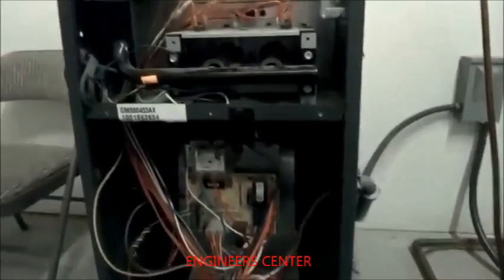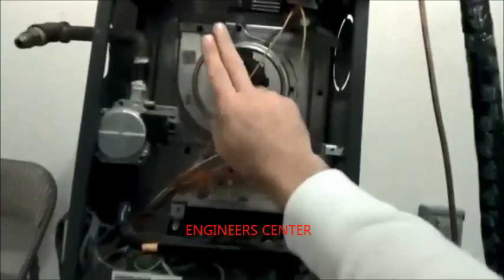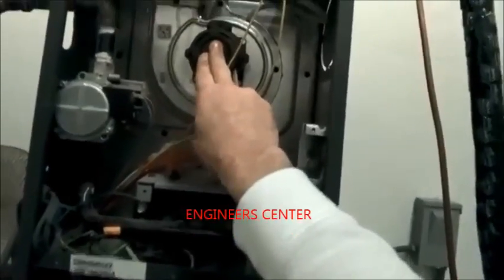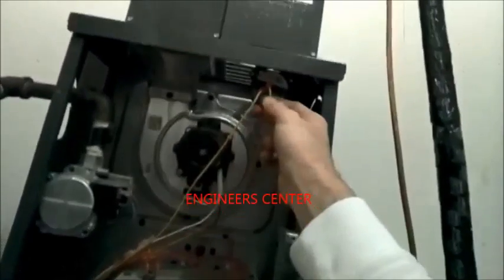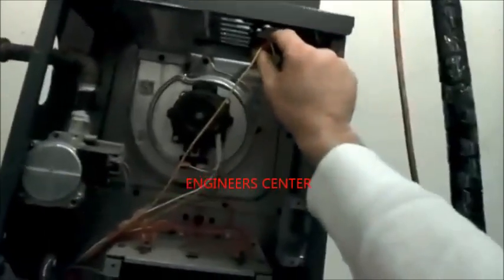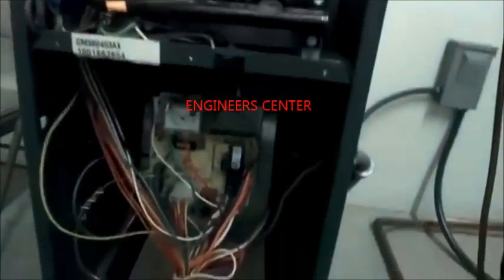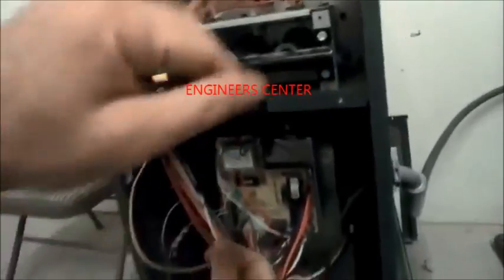And so you have to know the sequence of operation, because all I would do now is I would watch this furnace and know the sequence. If at any point I had a pause, let's say I had the inducer come on and then nothing else happened, I would start questioning the next step. I would say, well, did this sense that this opened or not? And so I would pretty much test to see if this thing was closed. If it was closed, I would move down to here and look at the board. I'd say, well, the pressure switch is closed, it's sending power back. I'd test the signal. I'd say, yep, the board should be knowing that the pressure switch is closed. Why ain't it bringing on the hot surface igniter? And so I'd come look at the hot surface igniter and maybe test its continuity. If it was bad, that'd be my answer. I would say, well, in fact, the board was sending power. You could even come to the clip and test power coming out of the board to the hot surface igniter, and you see if you have power. If you have power going to it and it's not glowing, it's bad. If there's no power going to it and this thing is closed, then your board's bad. Because you knew your sequence of operation, you could tell where it's failing in its step.